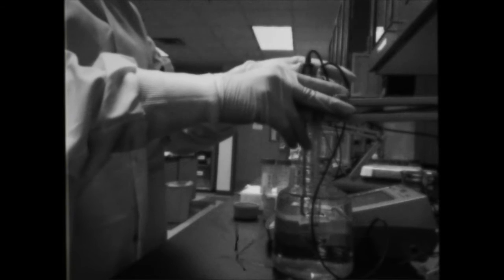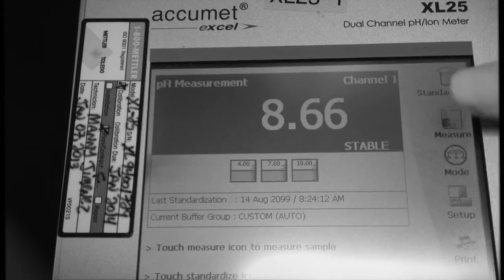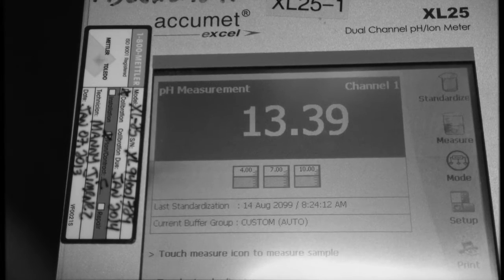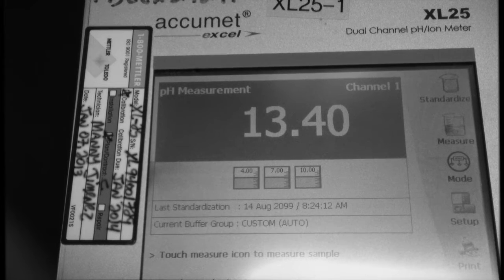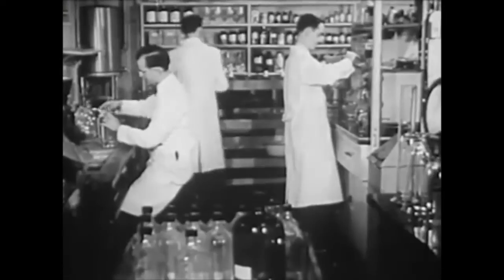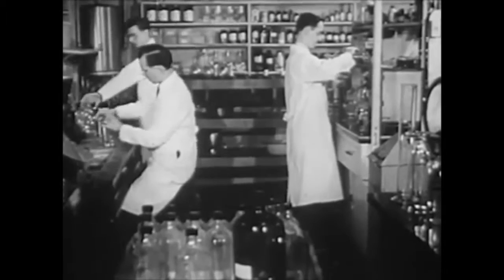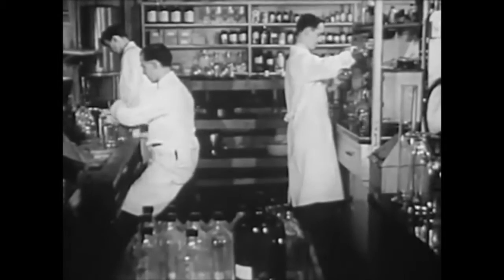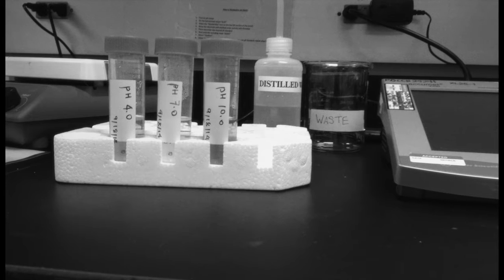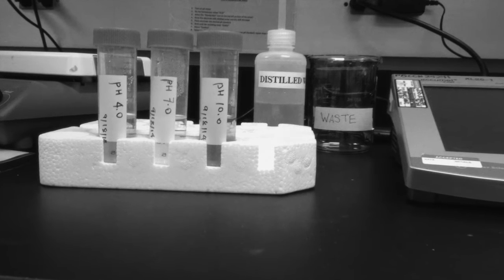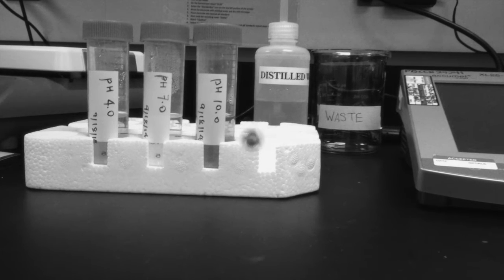The arm keeps the probe still to prevent disruptive currents. The computer box shows the readout as it happens, and the technician must wait for the reading to be confirmed. The probe is rinsed and stored in a special protective cover that keeps it moist so the readings don't go haywire. When operated by trained workers, this miracle device will give accurate readings every time, provided it's calibrated before each use with standard low, neutral, and alkaline solutions.